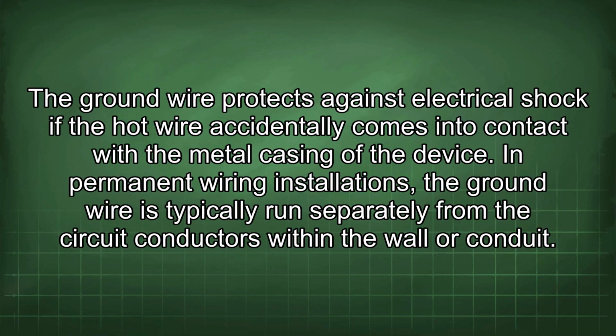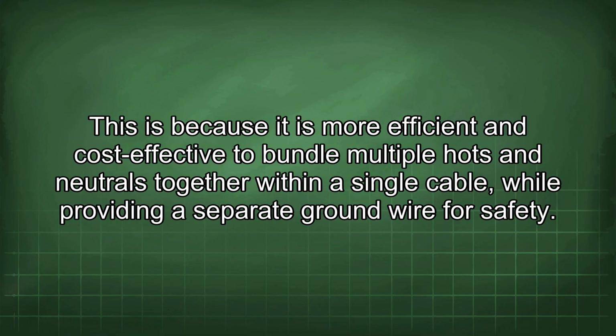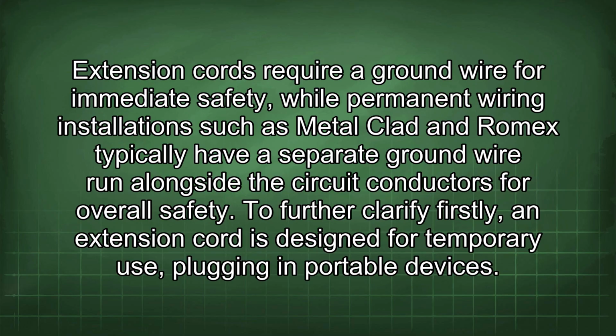In permanent wiring installations, the ground wire is typically run separately from the circuit conductors within the wall or conduit. This is because it is more efficient and cost-effective to bundle multiple hots and neutrals together within a single cable while providing a separate ground wire for safety. Extension cords require a ground wire for immediate safety, while permanent wiring installations such as metal-clad and Romex typically have a separate ground wire run alongside the circuit conductors for overall safety.